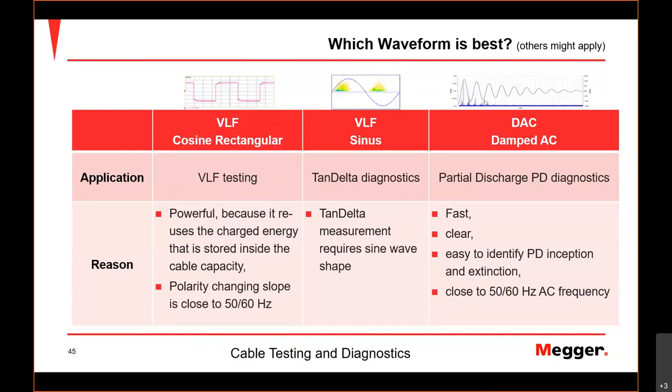So we apply a voltage of, let's say 200 hertz, for example, and during that frequency, we measure the partial discharge, display that, locate that. The nice thing of partial discharge is it's giving you a location. All these little dots here, these blue spikes here, they come up, they can be located. We will later see, right now this is just introduction, I will go into all these details again, but we can locate that. The principle is kind of like reflectometer, TDR, reflectometer measurement that we know from cable fault location. It's very closely related to that.